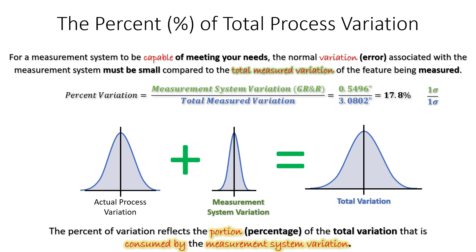One thing to note: unlike the precision tolerance ratio where we used six sigma, here we don't do that. For percent of total process variation, we just take one standard deviation divided by one standard deviation. There's no need to do the whole six sigma or 5.15 sigma conversion — we're literally just comparing two measures of standard deviation against each other.